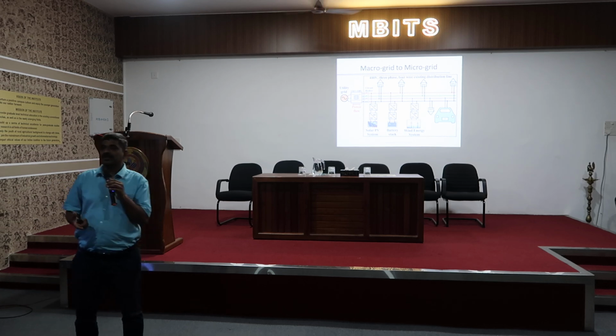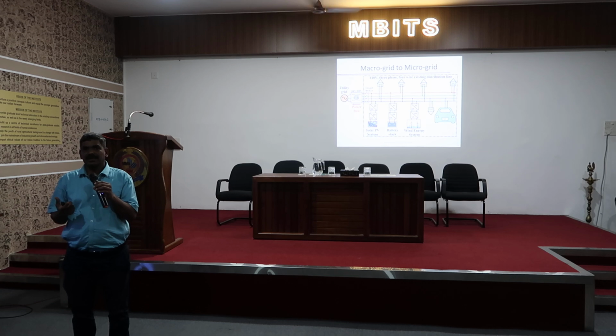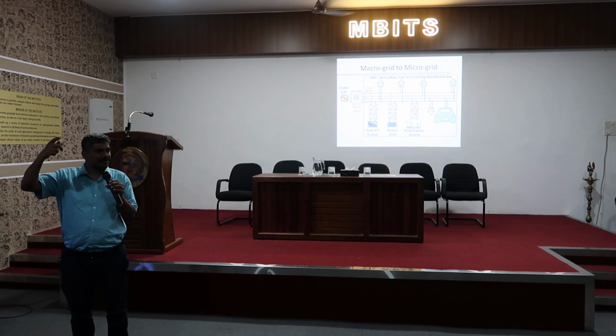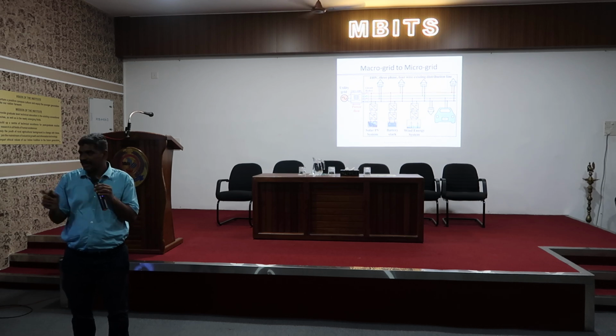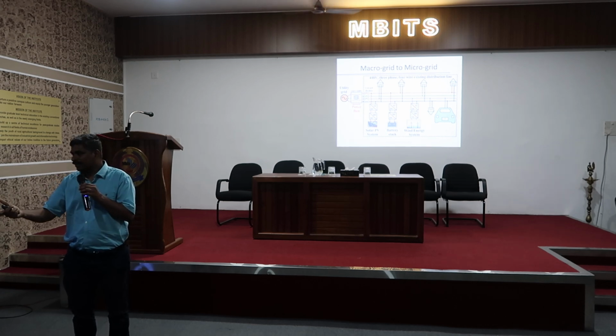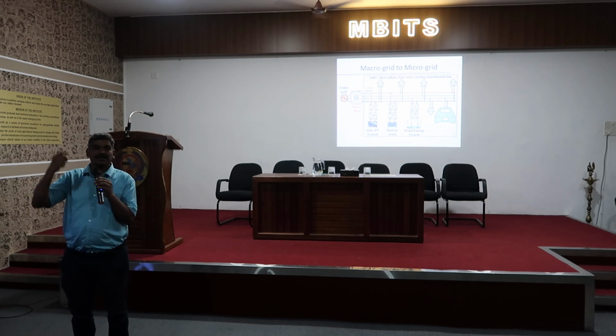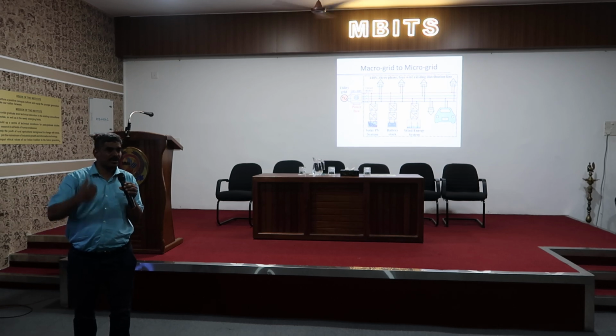Not only that, the main thing is core loss. Core loss is sometimes proportional to frequency - there's a numerical value for it. So that also increases because the fundamental frequency is 50 Hz, but the third order harmonic is 150 Hz. So naturally the losses significantly increase and the transformer overheats.